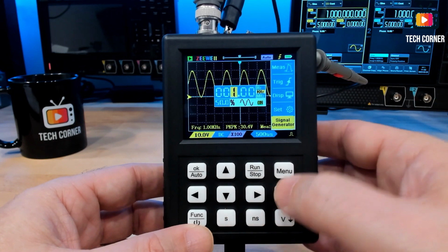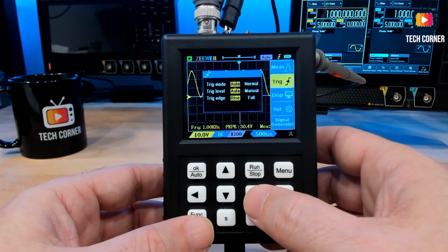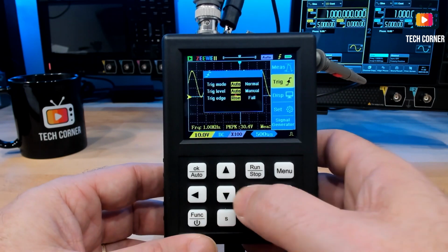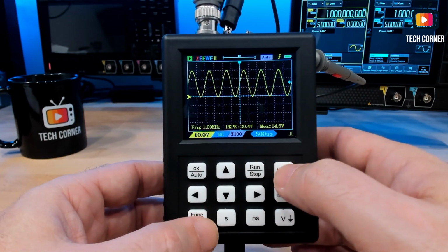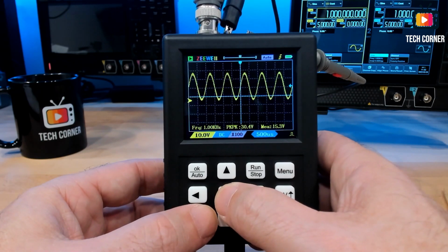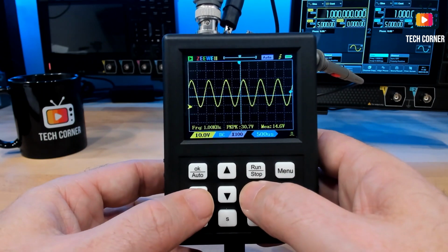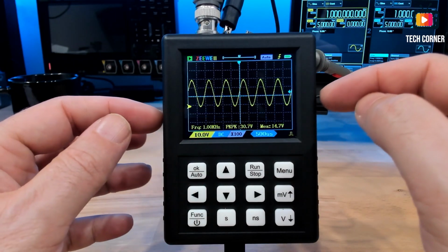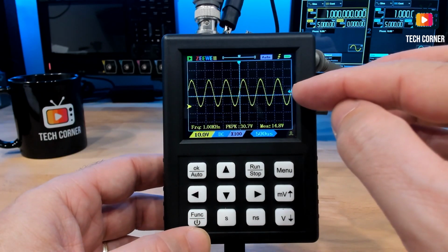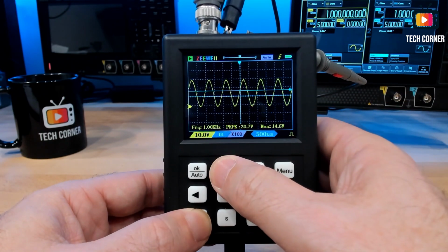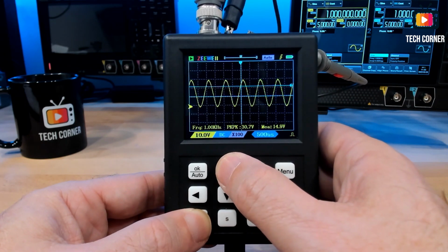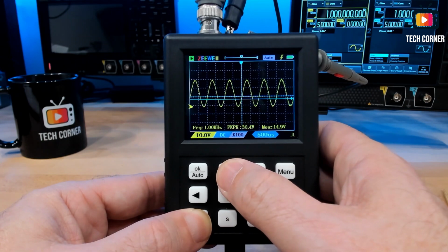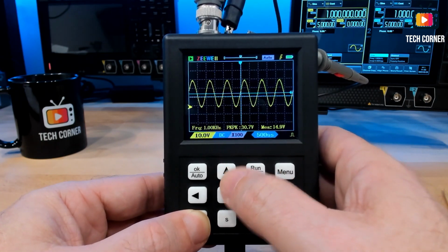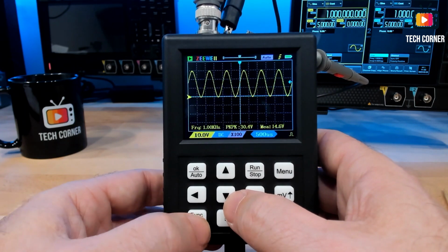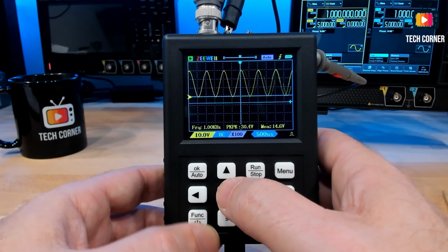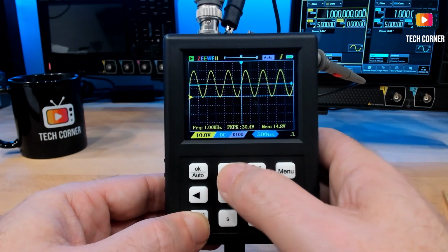We will go here to the trigger menu and change the trigger mode, now trigger level to manual. Okay, now it's manual. Let's take it out. And if you use the keys to move up and down or to the right or left, you will be able to move the signal and the signal in the sample memory. But if you want to move the trigger, you just press function and the direction keys, and you can see that the trigger is moving. So that's how you move the trigger in manual mode. Okay, function, let's put this at 50%, and now you can move the trigger again. As you can see, it's out of the signal.